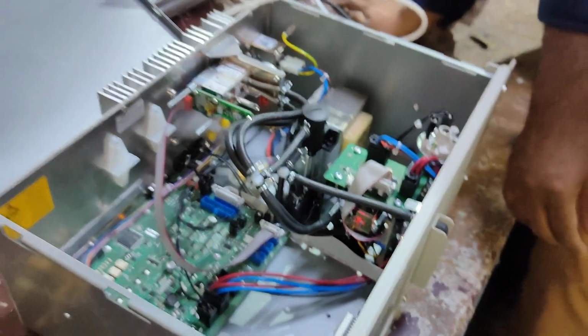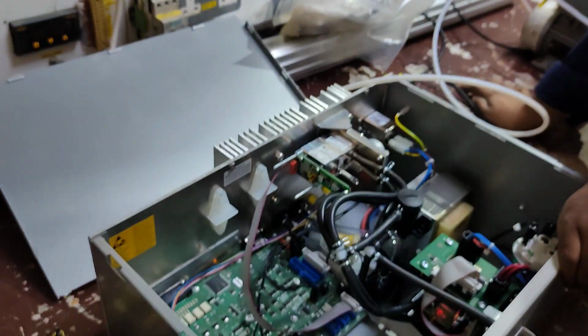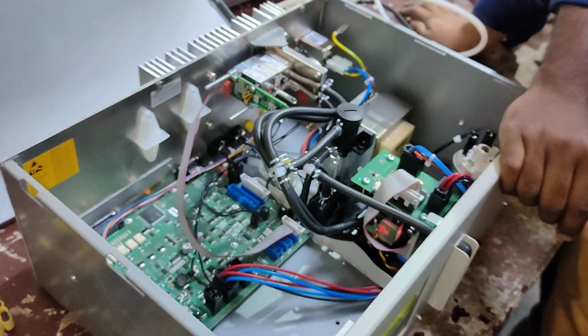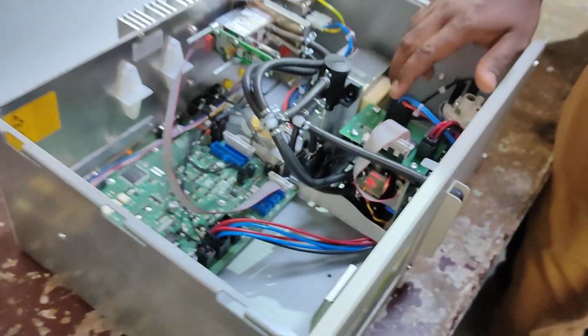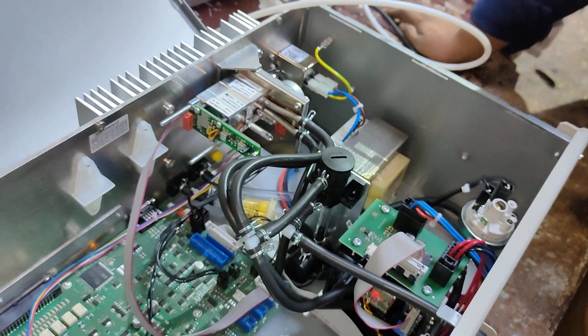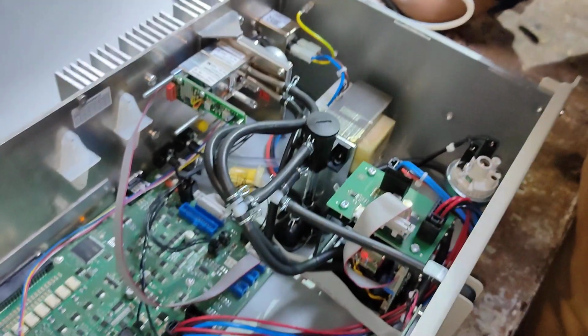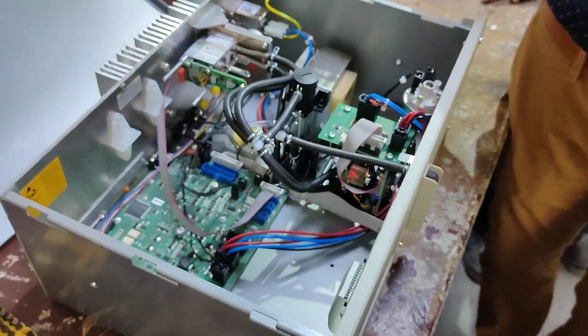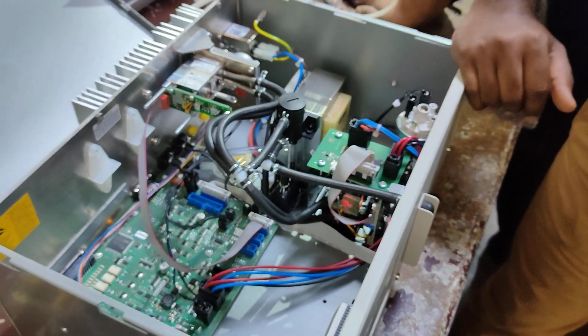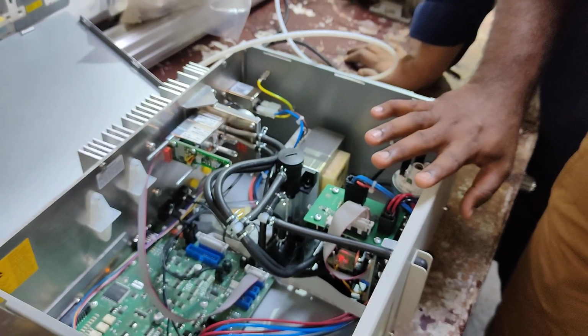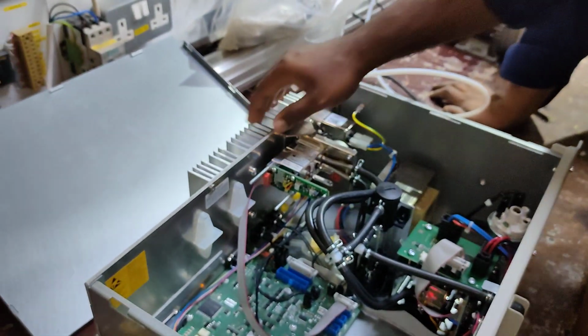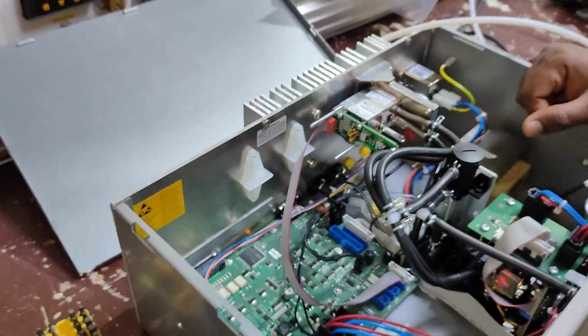In the last one, the Oxymat, we had a sampling chamber. You replaced that one last time. Is it available in this one? No, nothing. It is not there at all, because with no nitrogen and no reference, there is no difference happening. So you don't need a sample cell as such. We don't have the sample cell here because we are not running nitrogen as a reference. If you have any problem, you have to replace the full unit.